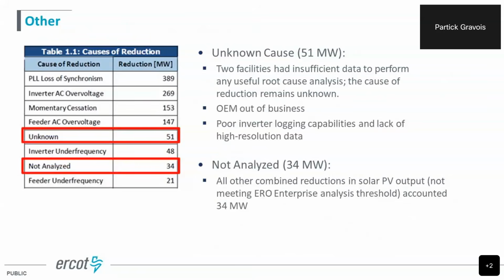The rest, we had some unknown issues. We had some older inverters that had an OEM that is now out of business. So it was very difficult to find who took over the service contracts and what we could do to improve the logging capabilities. They also had a lack of PMU data or high resolution relay data. So we're really unable to determine the root cause of these reductions. So it was 2 facilities that were unknown.